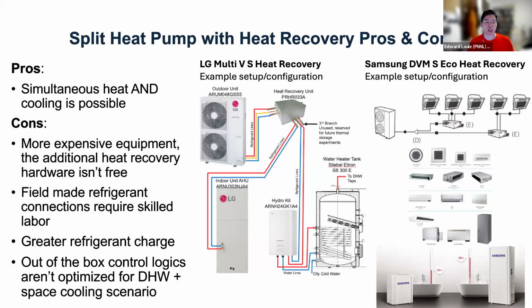But when you have domestic hot water paired with space conditioning, then the temperature difference between those two zones is pretty significant, and the out-of-the-box control logics on these pieces of equipment aren't currently optimized for domestic hot water and space cooling scenarios. But at PNNL, we're working with some of the manufacturers to optimize the control logic. So in the near future, we think that control issue will be solved.